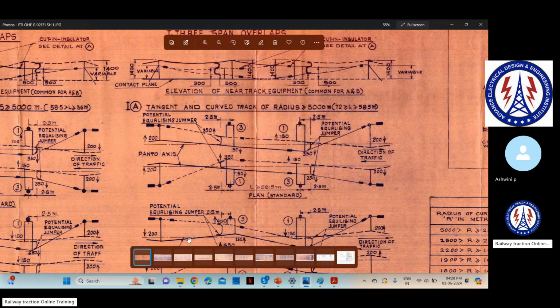That is there. Okay. But when you go on the site, you cannot see the stagger, right? What you can see is this jumper and this insulator. You have to find it on that itself. Am I right? Because you have to measure the stagger, then only you can come to know. Without measuring, I'm just saying, by just looking at it.